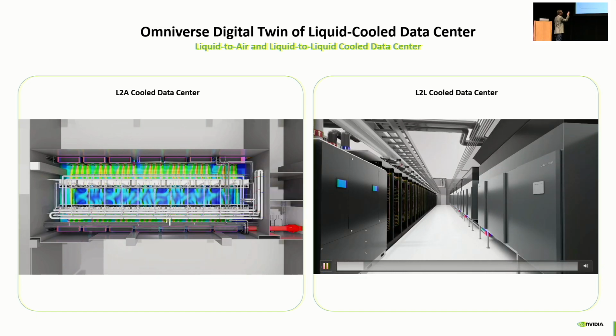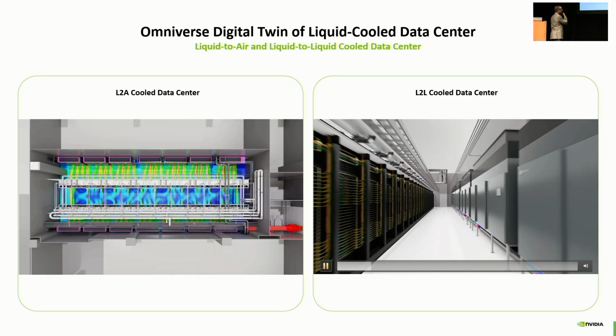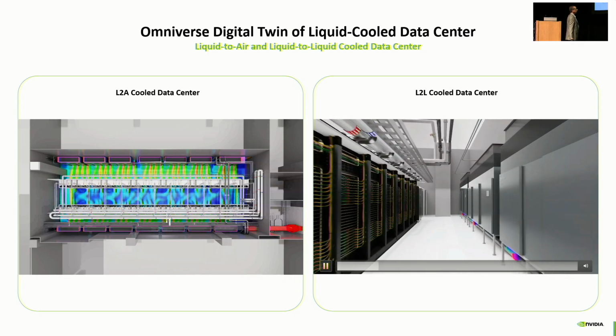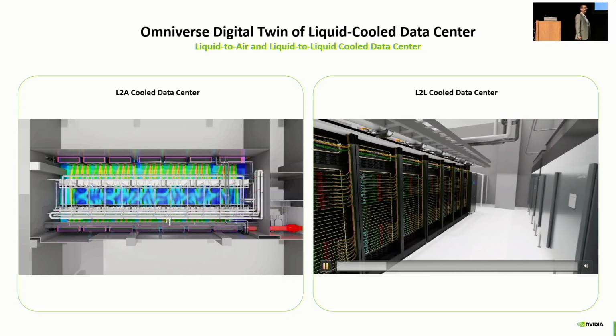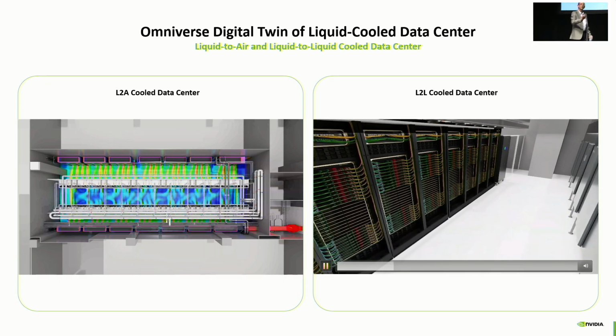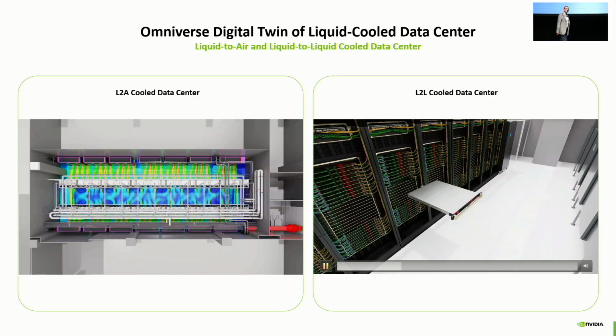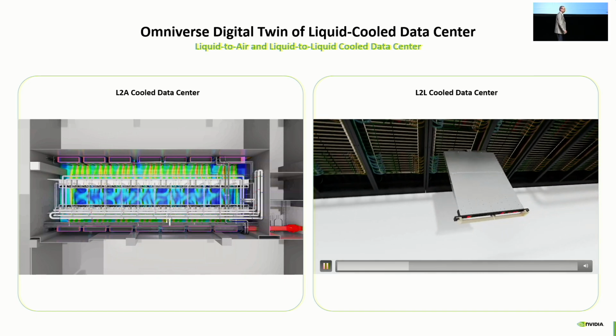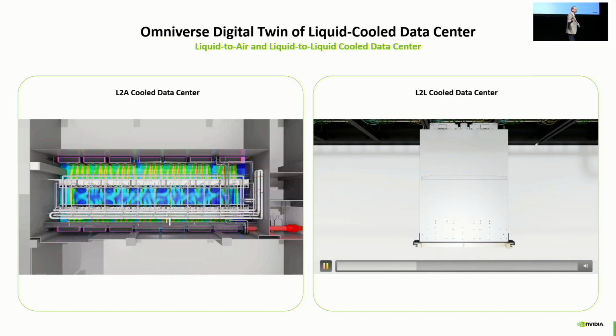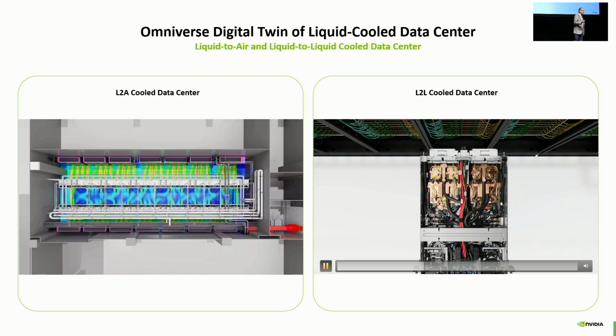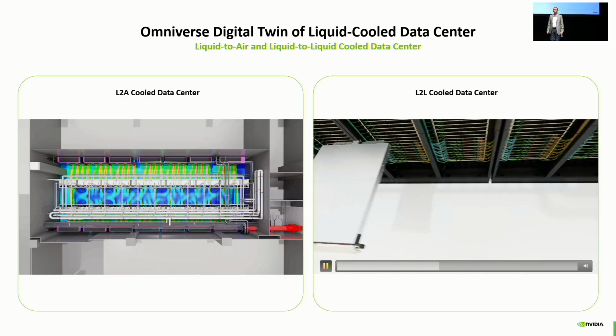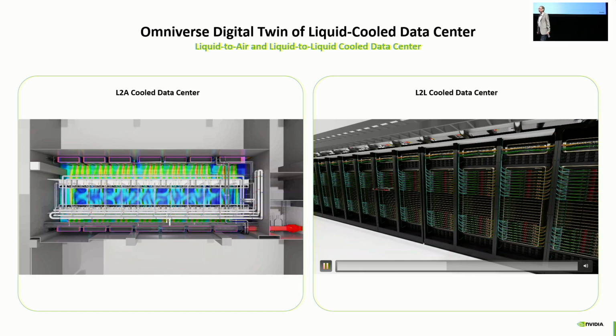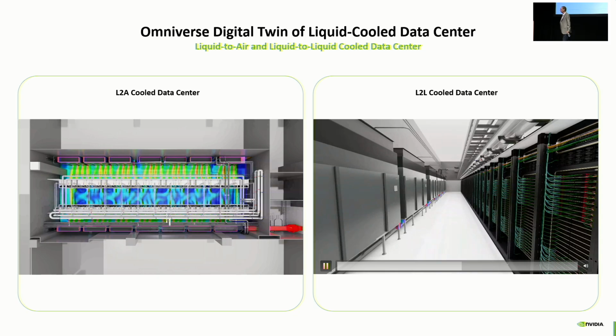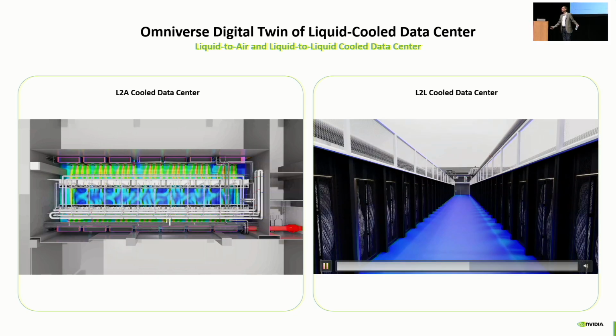You can see on the left side the CDUs and the row of racks, row of CRAH units. You're pushing about 85% of heat to the liquid. We're taking 15% of the heat from the air. The liquid plumbing shows how the plumbing removes the heat with the CDUs from each one of these racks, with the GPUs cooled by cold plates attached to them, with manifolds distributing liquid inside, and the CRAH units that remove residual heat.